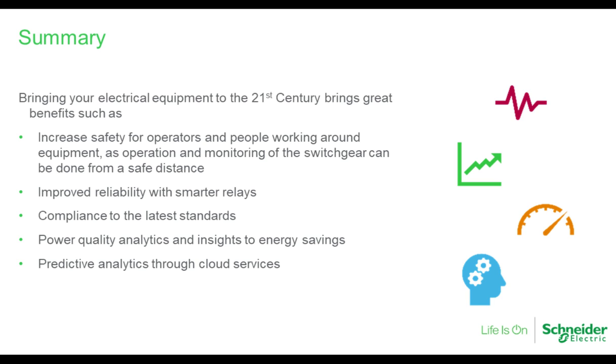And also compliance to the latest standards. Standards have changed over the years. And now with some of these new and retrofit equipment and modernizing of equipment, we can meet some of the new standards that exist. I mean, one of the new standards is some type of energy reduction at 1200 amps and above. We can now meet those with upgrading and modernizing the existing equipment without replacing it.